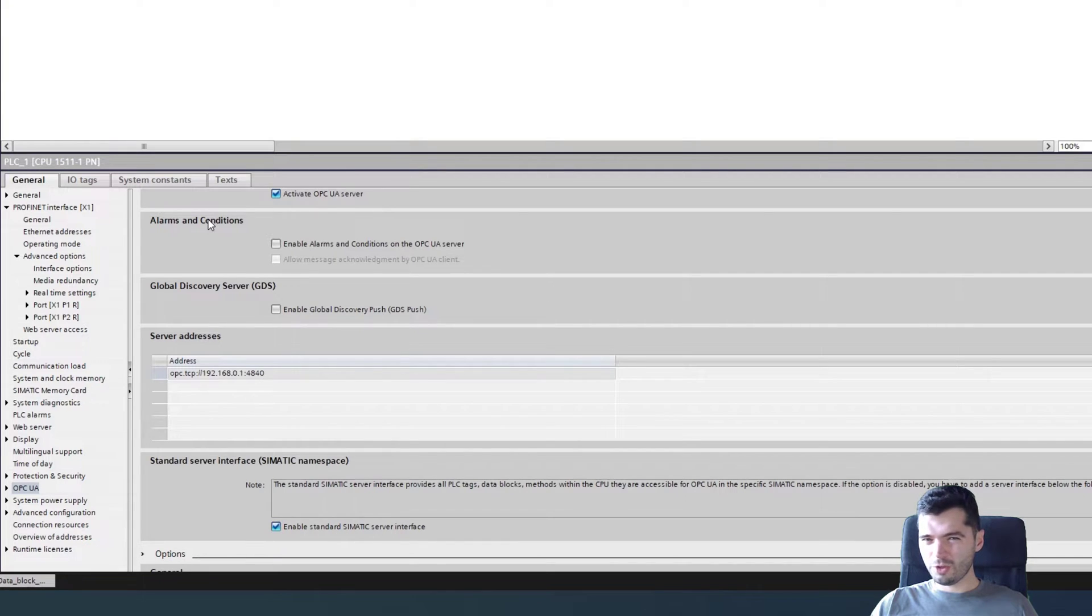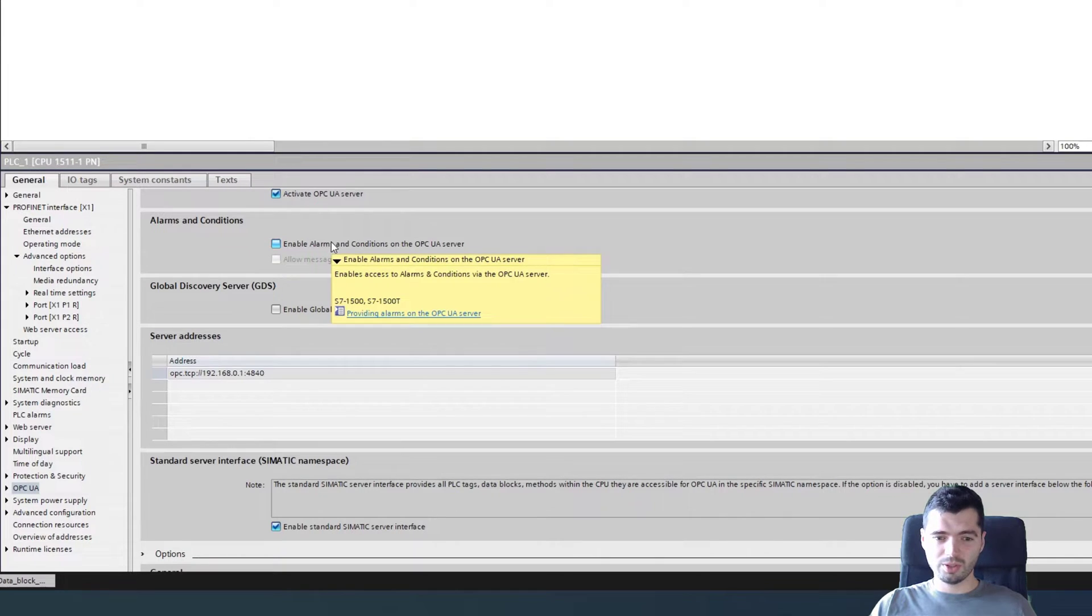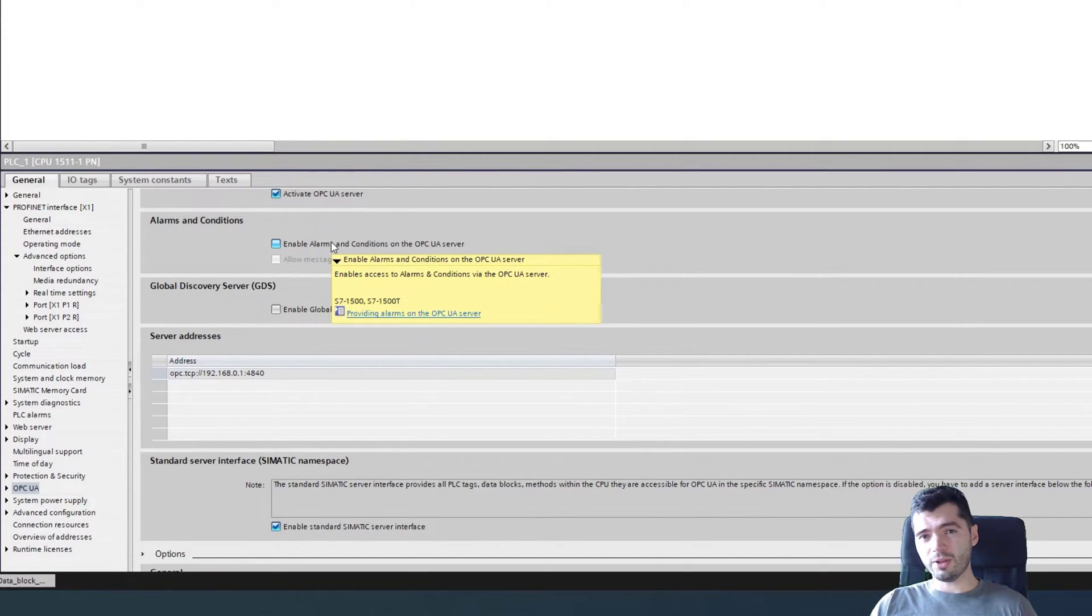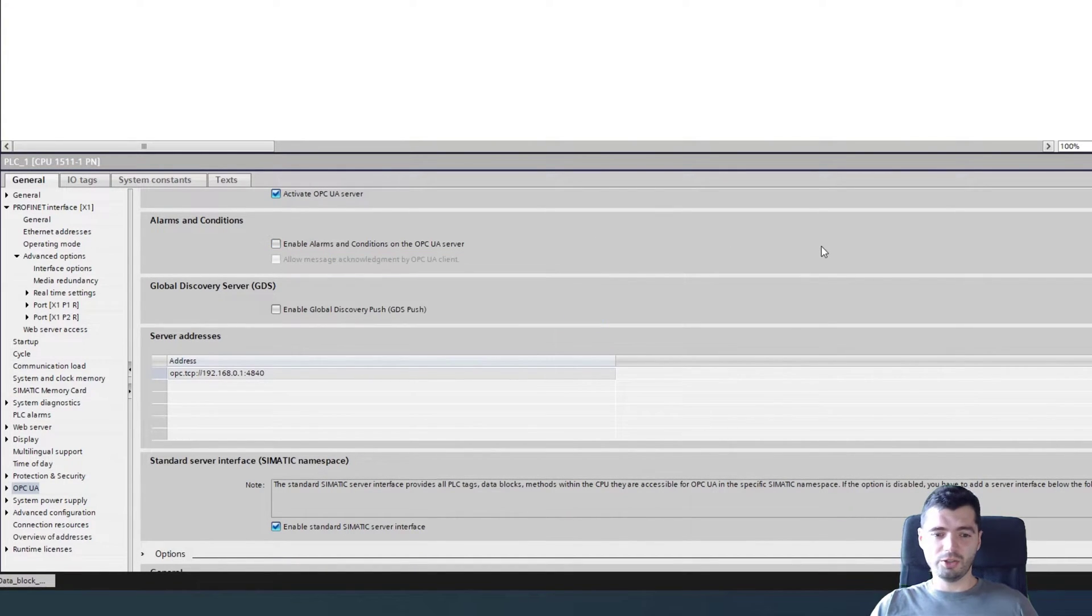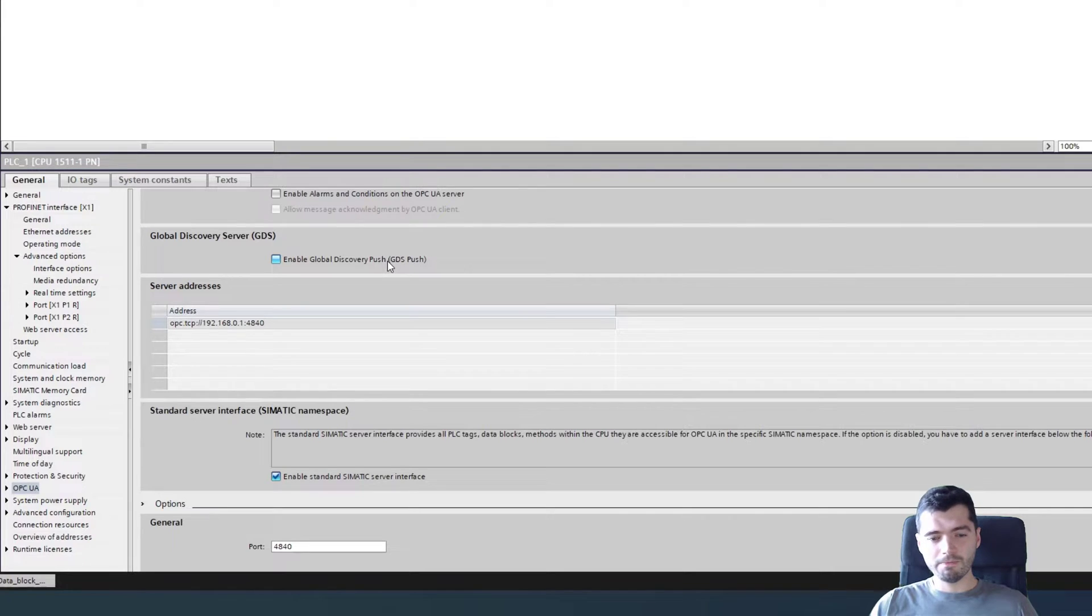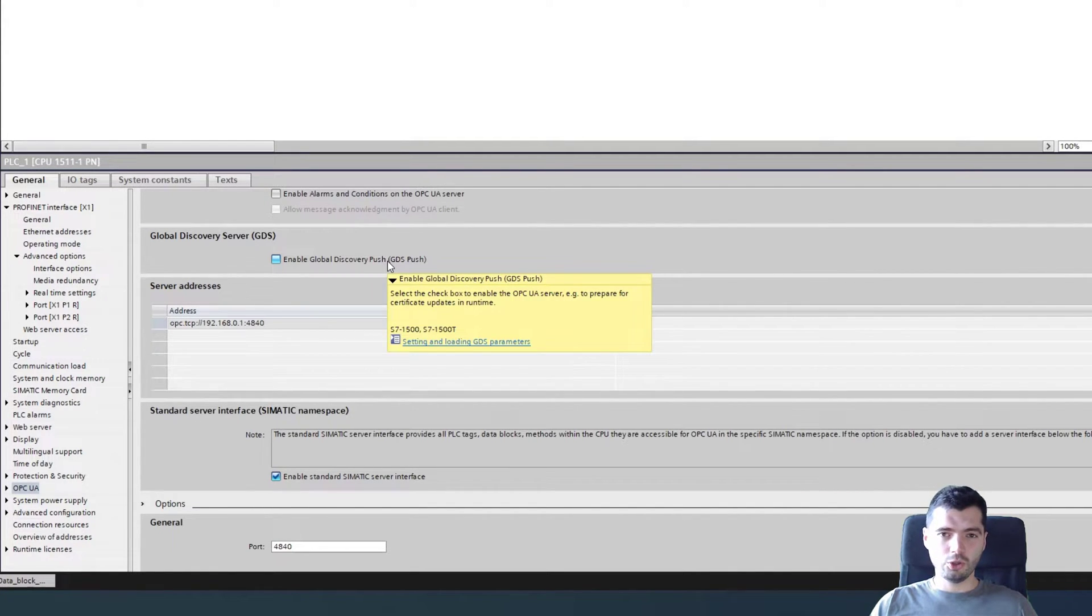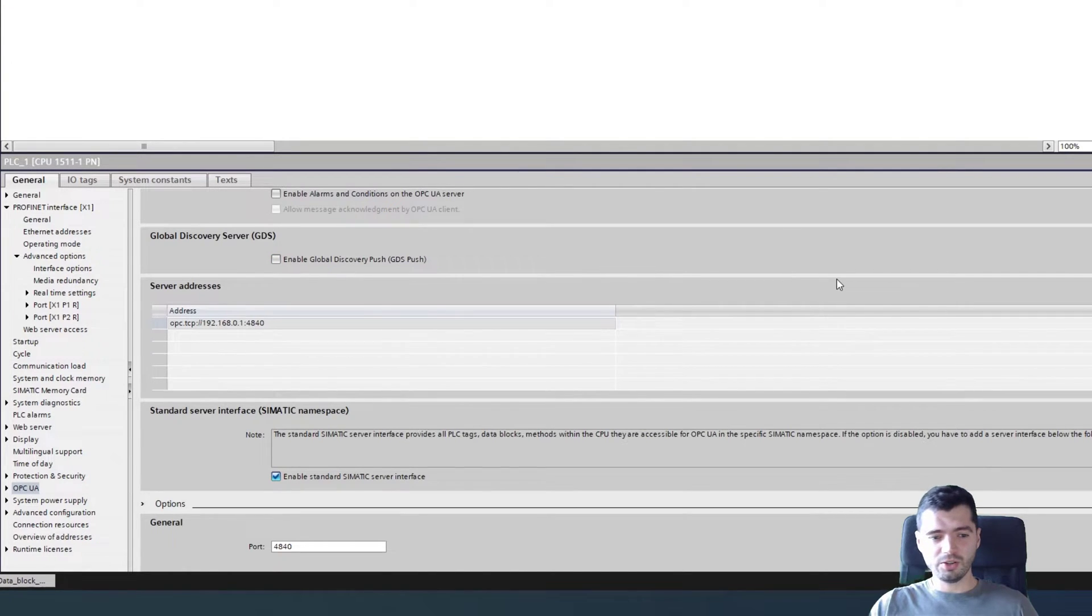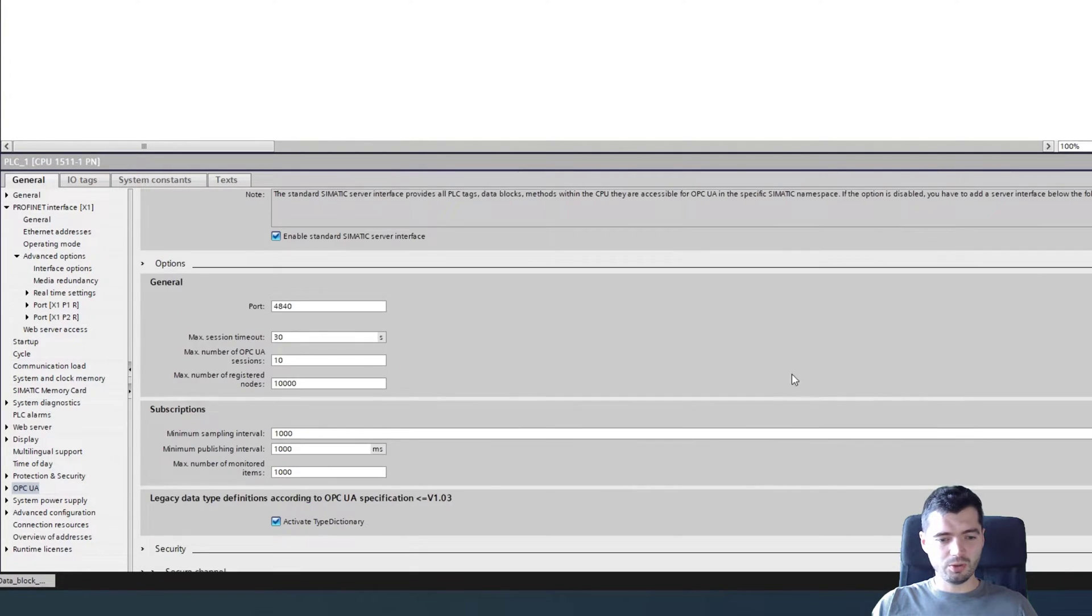With version 2.9 of the OPC UA server, alarms and conditions were enabled as well. So this actually allows you to expose PLC alarms, things like program alarms as well via the OPC UA server. And GDS push is for using external tools to load certificates onto your OPC UA server.